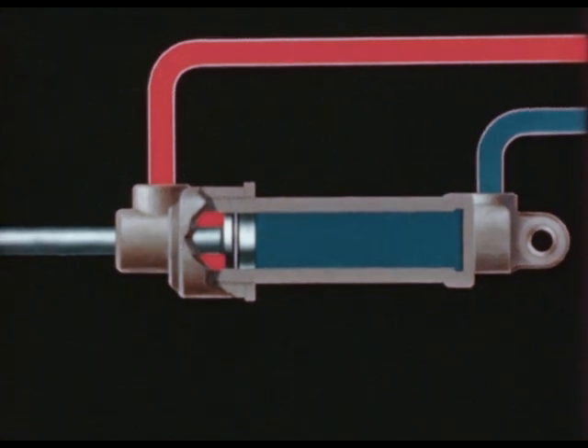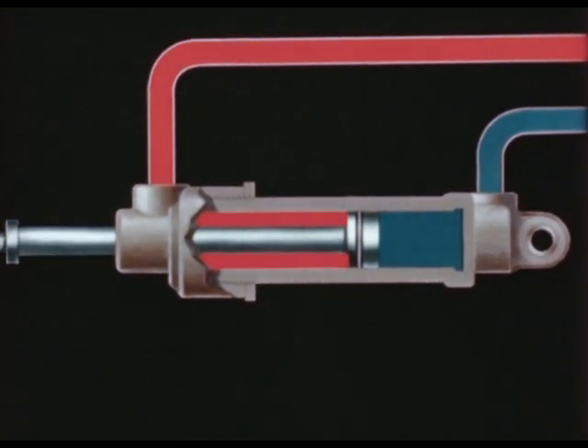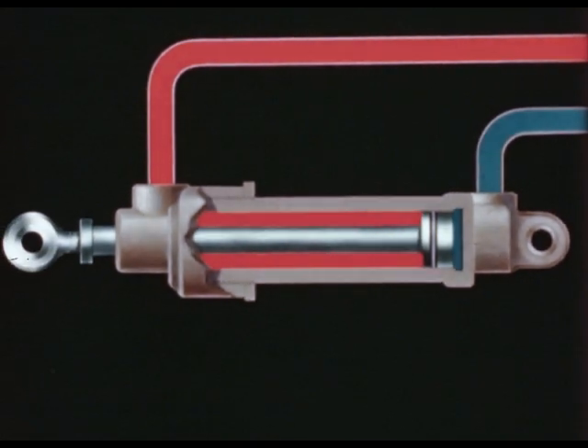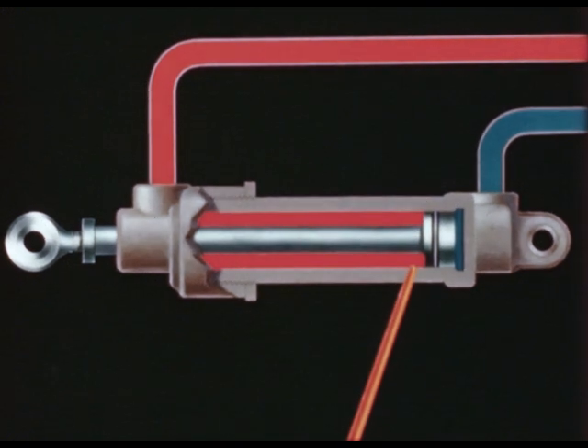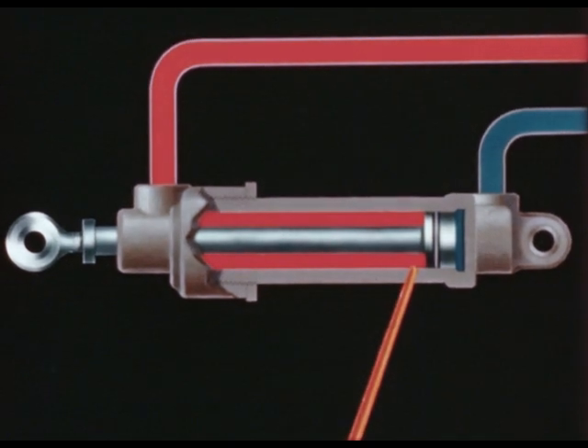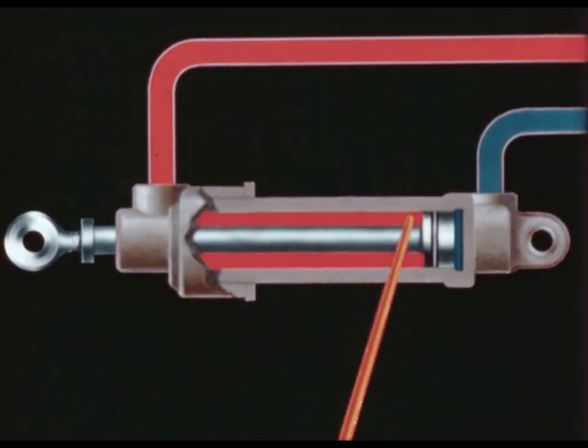The pressure on the fluid in one end of the cylinder causes the piston to move. This movement forces the fluid out of the other end. The force on the piston depends upon the pressure generated by the pump and the area of the piston. The speed of the piston depends upon the capacity of the pump and the volume of the cylinder.